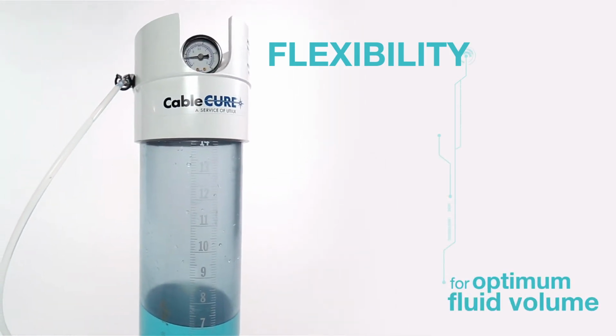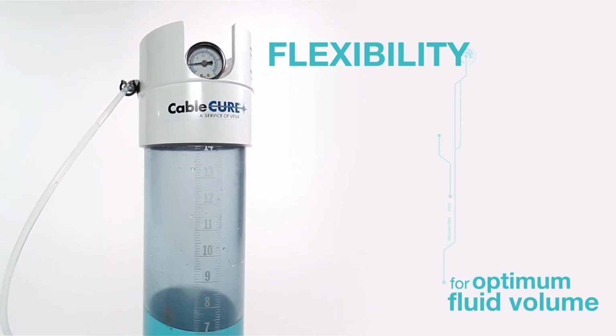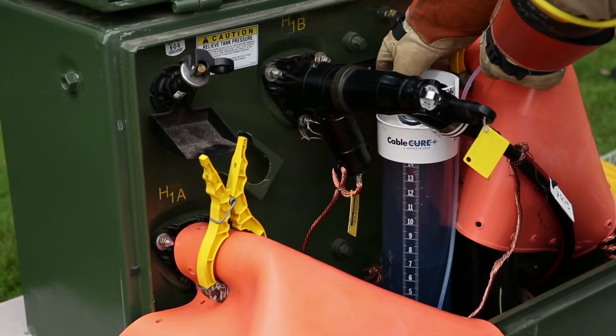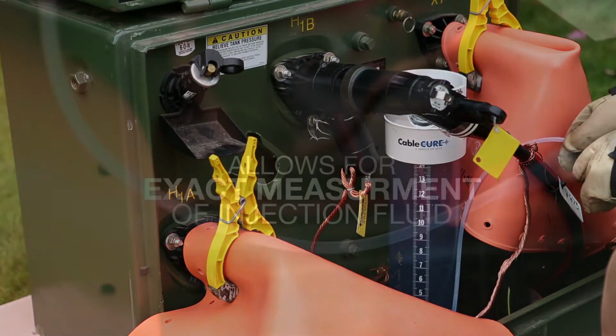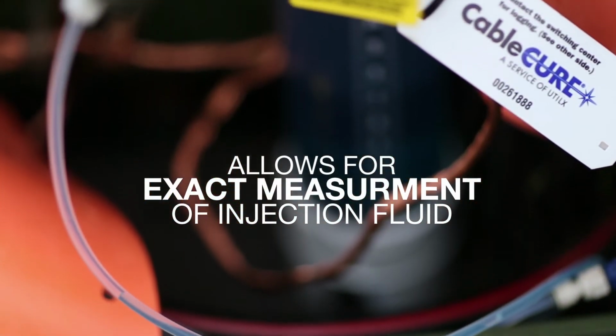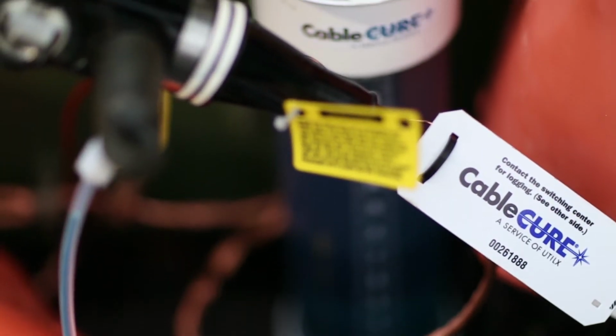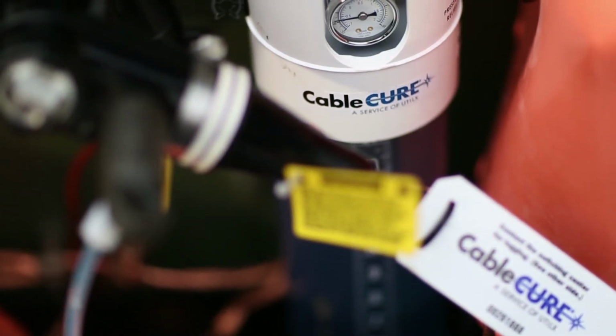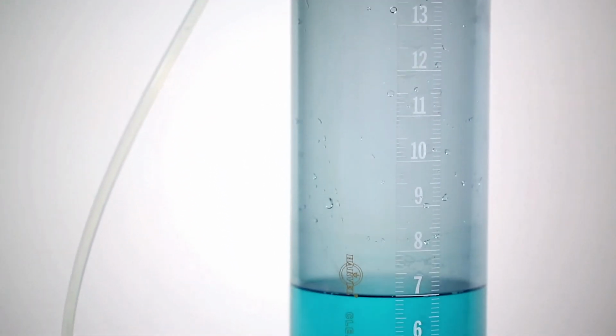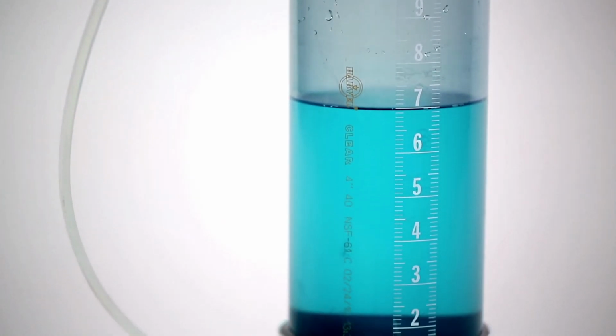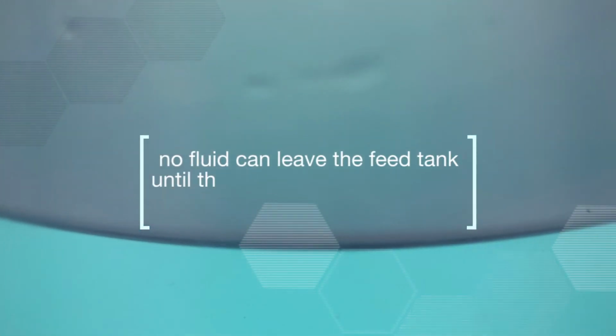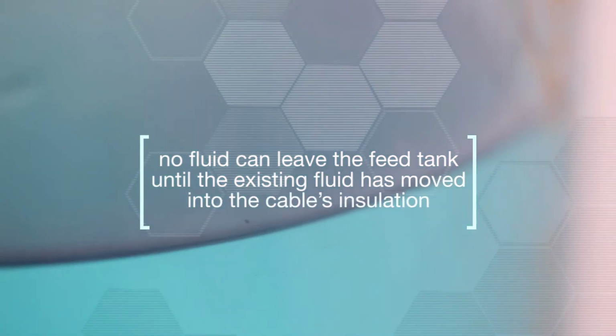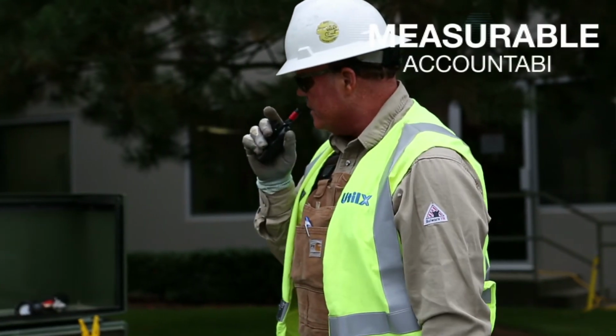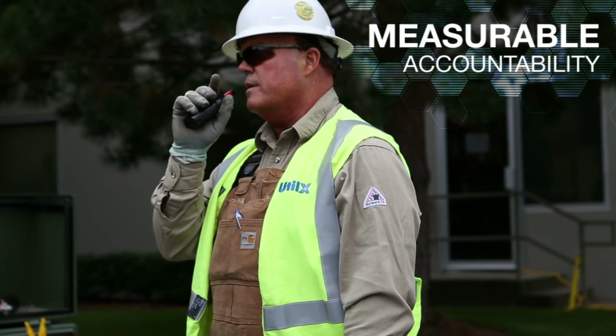It is indisputable that a low-pressure feed tank provides the flexibility necessary to supply the optimum fluid volume to each and every cable geometry. The feed tank provides another equally important function which may not be immediately obvious. The feed tank allows the exact measurement of the fluid that actually diffuses into the cable's insulation, not just the fluid that was put into the cable strands. Since the cable's interstitial spaces are already filled with injection fluid when the feed tank is installed, no fluid can leave the feed tank until the existing fluid in the cable moves into the cable's insulation. This provides measurable accountability that should be required of all engineered systems.